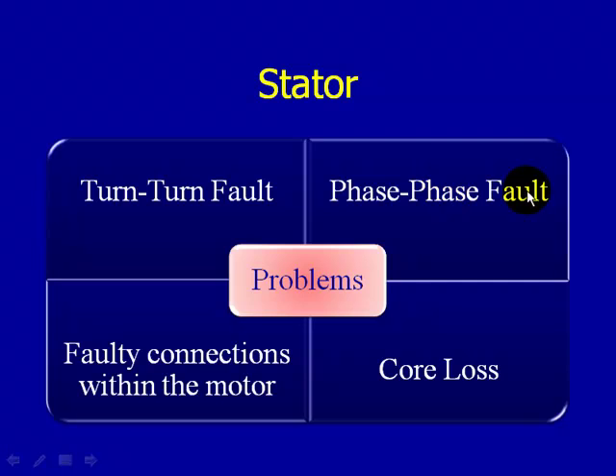What are some of the problems in the stator fault zone that can occur? You can have turn-to-turn fault, phase-to-phase fault, faulty connections within the motor, and core loss. Keeping in mind the six fault zone approach — when we look at the power circuit, we're trying to make sure the whole power circuit is evenly balanced. Any type of unbalance could create excess heat in the circuit, and that excess heat could destroy insulation, potentially causing a turn-to-turn fault or phase-to-phase fault as that insulation breaks down.